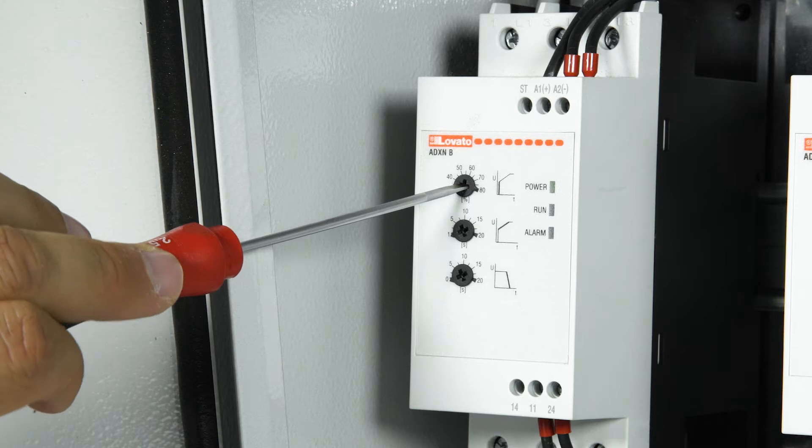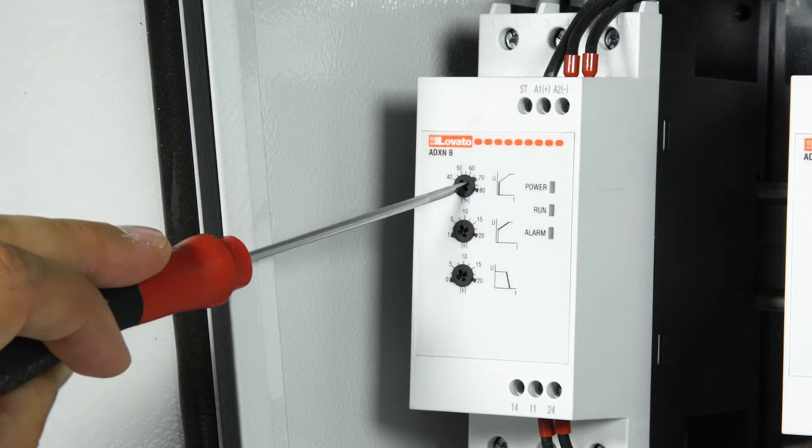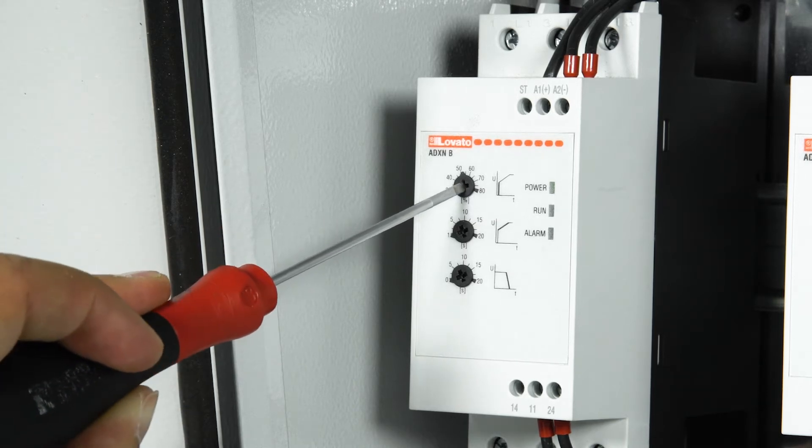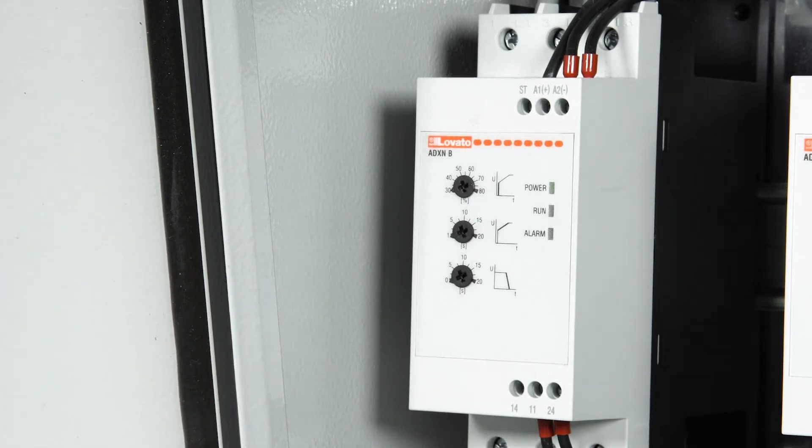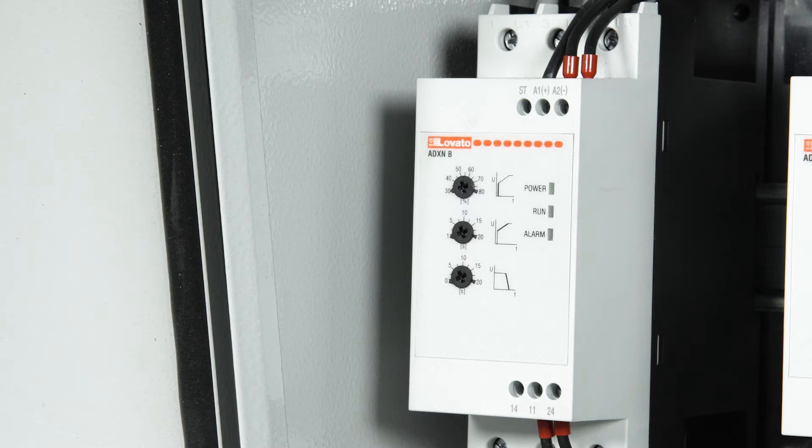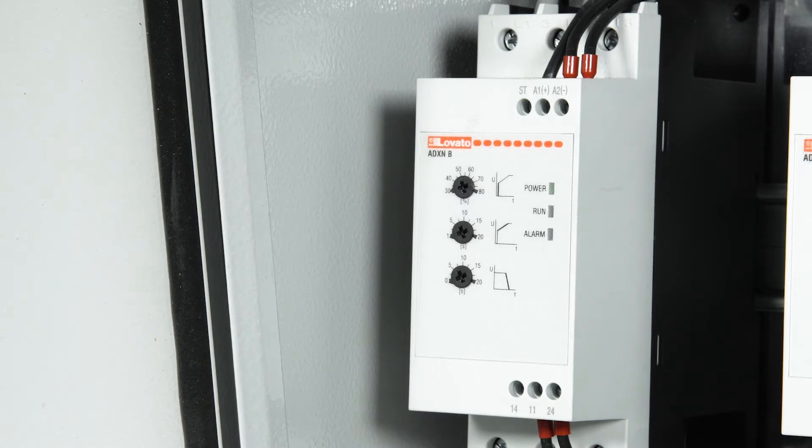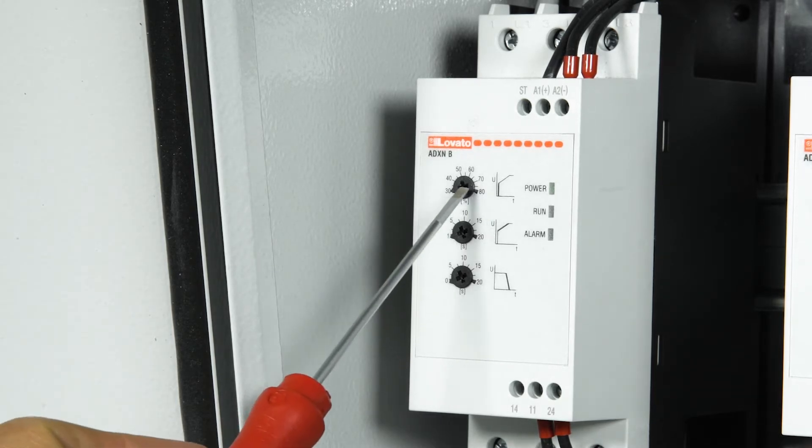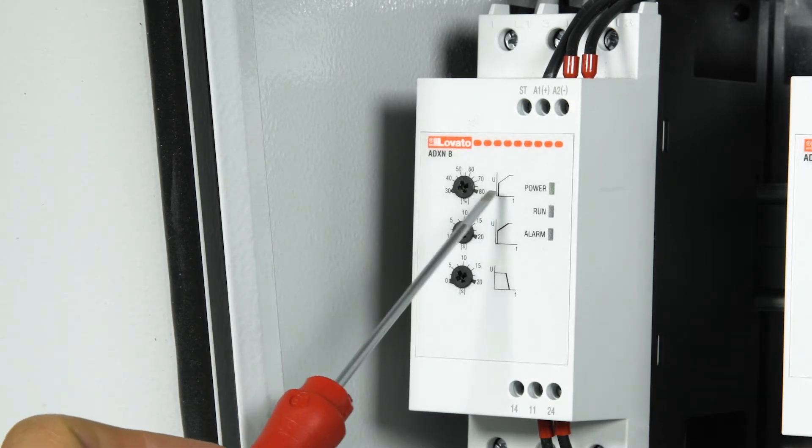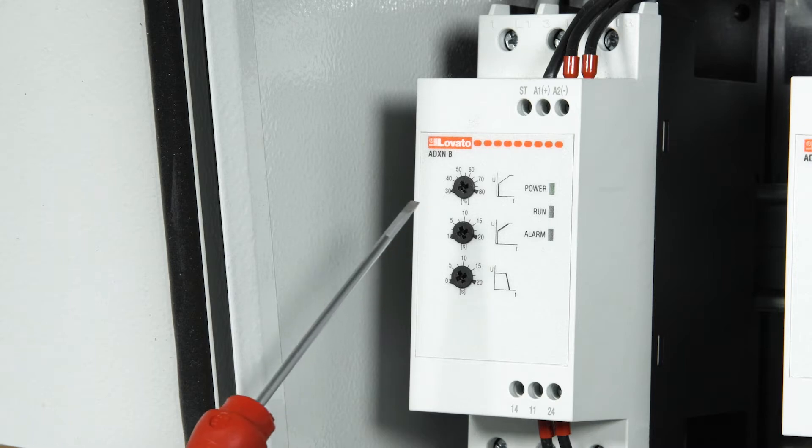It should be set so that the motor starts running slowly immediately after the start command, which depends on the type of load controlled by the soft starter. The higher the step, the higher the torque that is applied to the motor.